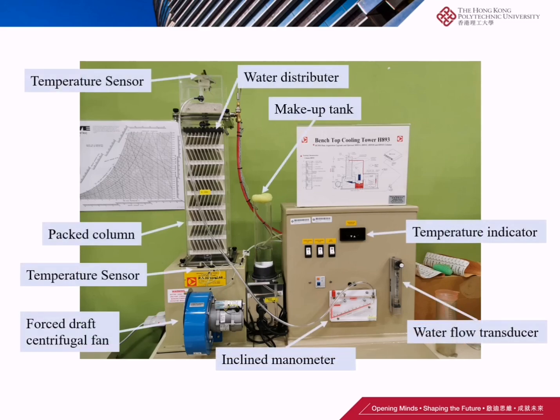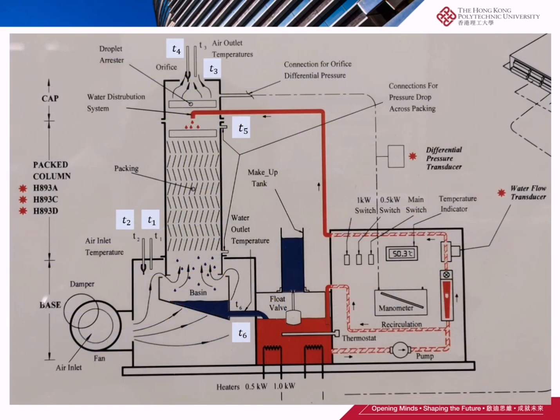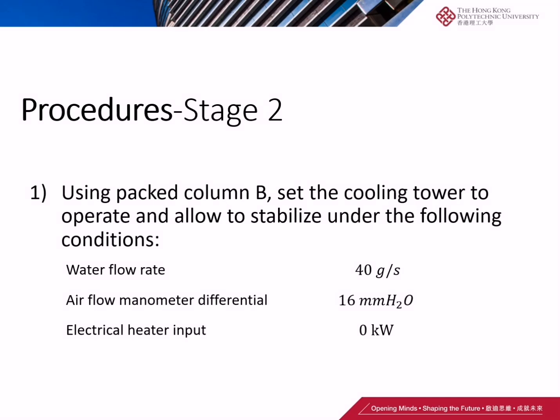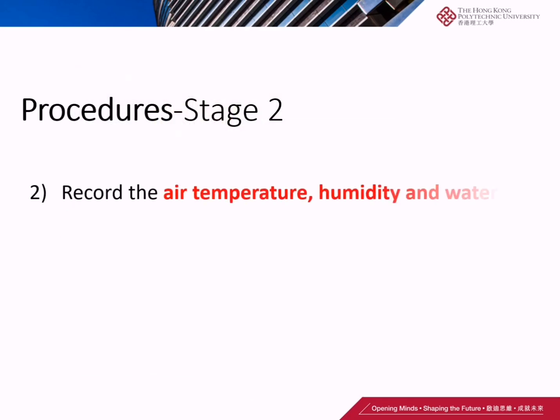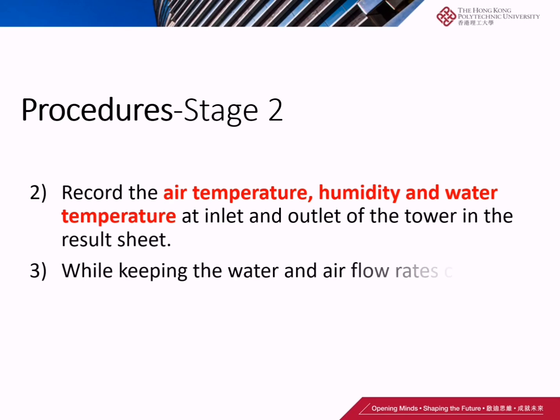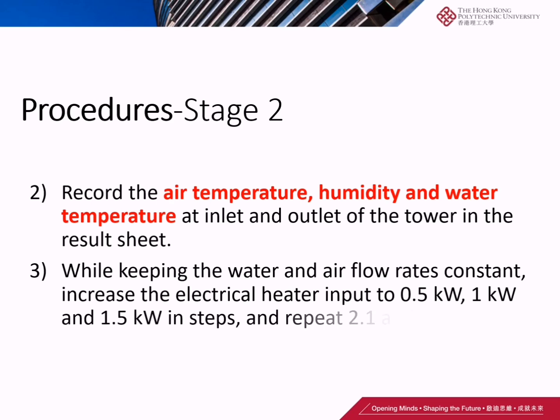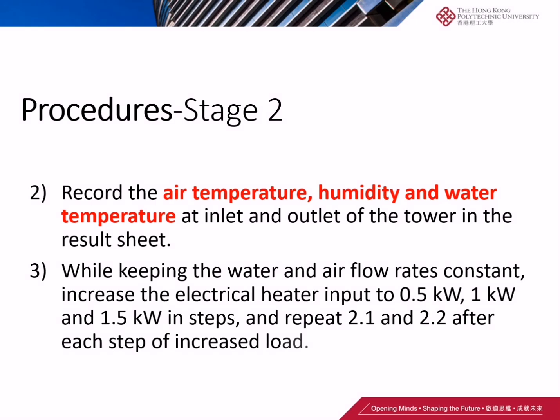Here is the picture showing the whole attached rig. In Stage 2, using packed column B, set the cooling tower to operate and allow it to stabilize under the following conditions. After stabilizing the test rig, record the air temperature, humidity, and water temperature at the inlet and outlet of the tower in the result sheet. The last step in Stage 2 is to keep the water and air flow rate constant and increase the electrical heater input to 0.5 kilowatt, 1 kilowatt, and 1.5 kilowatt in steps, and repeat steps 2.1 and 2.2 after each increase in load.